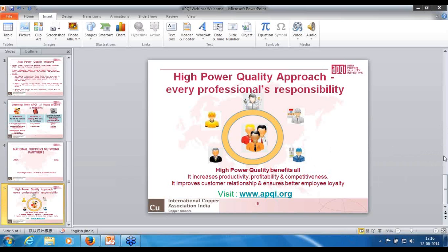Another experience I can share: one of the network service providers, BSNL, inside the processor they work at a very low voltage, 1.3 volts. And the neutral to earth voltage, because of the unbalance, reached more than 5 volts. There was damage, and the server got tripped. For just 5 minutes of server downtime they had to pay some 10.5 crores, because the server was down, Yahoo was down, and they had to pay a huge penalty. So they were asking whether we have any solution for a similar kind of application. It is very much available today, and there are many companies providing this kind of solution.